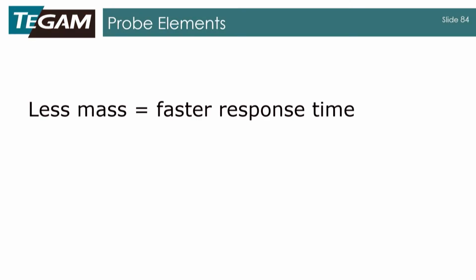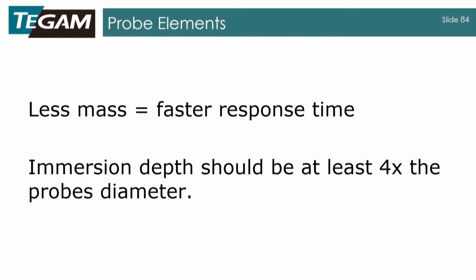Put it back to simmer. All right, so the main things to glean from that was with the less mass, we had a faster response time. And I don't know if you could tell, but I was being very careful to make sure that the immersion depth was at least 4 times the probe diameter on the one with the sheath. And that's how we were able to see that if I were moving it up and down, you would have noticed that when it reached that temperature, it would have started fluctuating. And I know this from personal experience. So it is important to get at least 4 times the probe's diameter, or it's going to see that outside air, and it's going to start to affect your measurement.